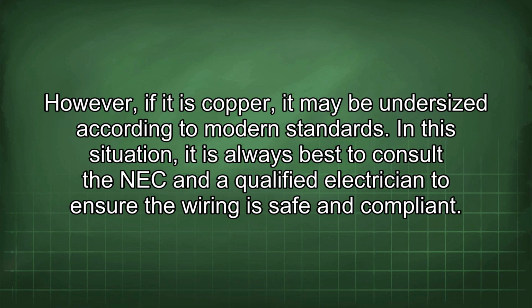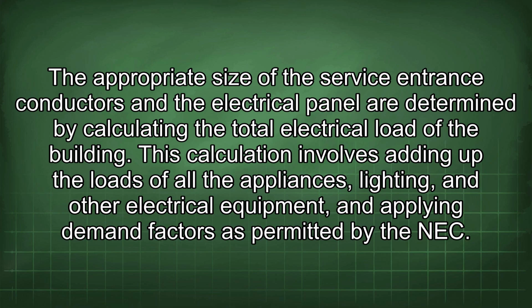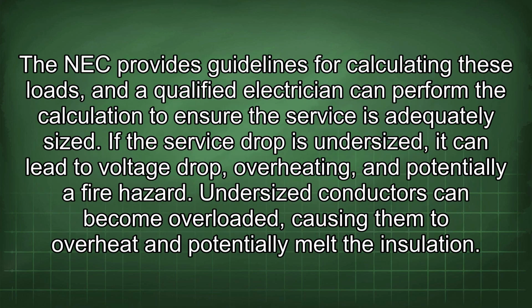In this situation, it is always best to consult the NEC and a qualified electrician to ensure the wiring is safe and compliant. The appropriate size of the service entrance conductors and the electrical panel are determined by calculating the total electrical load of the building. This calculation involves adding up the loads of all the appliances, lighting, and other electrical equipment, and applying demand factors as permitted by the NEC.